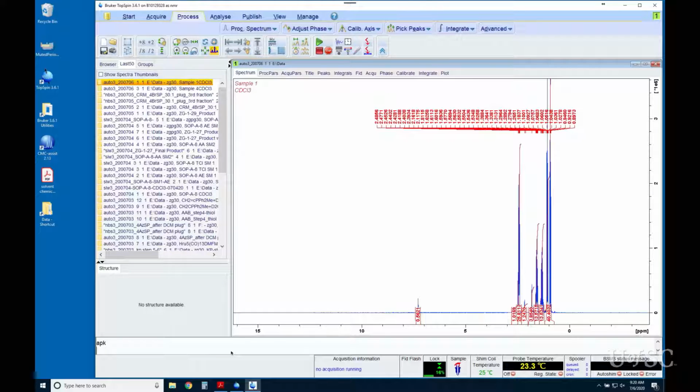We will discuss some of these here. When ICON NMR processes your spectrum, it will run the command SREF. This command looks for the presence of TMS and sets it to 0 ppm. If it does not find a peak near 0 ppm, it will use the default referencing. This is based on the instrument's lock frequency and the solvent. If you chose the correct solvent when you set up the experiment, the default referencing is usually pretty good and within about 3/100ths of a ppm of the correct value. For most results, this will be more than adequate.